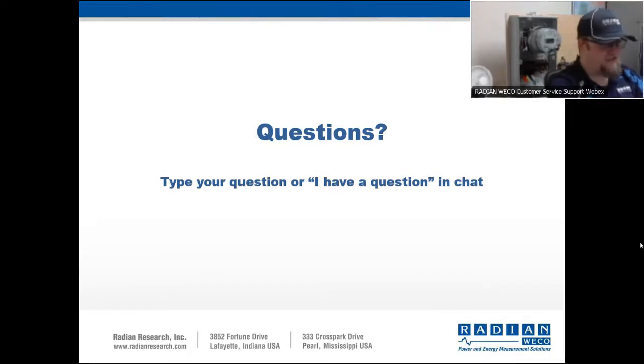The reason for that being, we let the utility make a call on what passes and what fails as a CT, versus our equipment being black and white and saying you have a failed CT. CT test results can then be used to bring up to your utility or yourself or whoever you're working with to determine, hey, is this CT something we need to address, or is this something that is acceptable for this service? So, unfortunately, there's no green or red check mark for these.